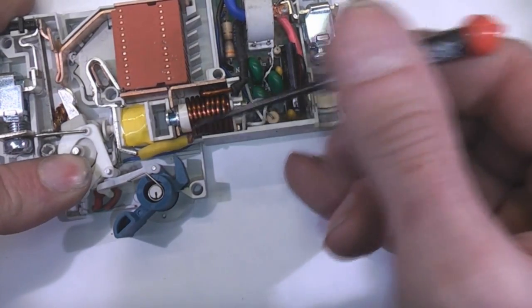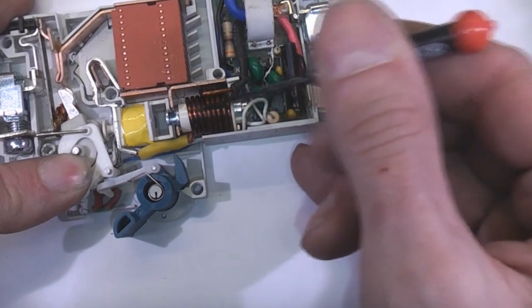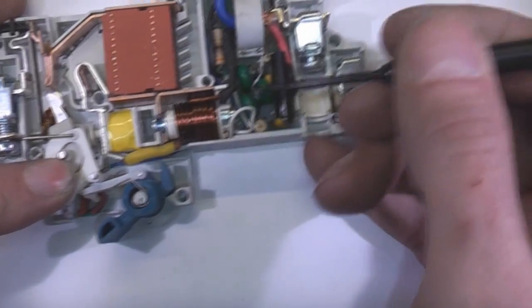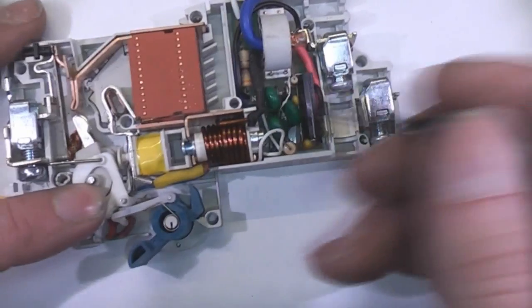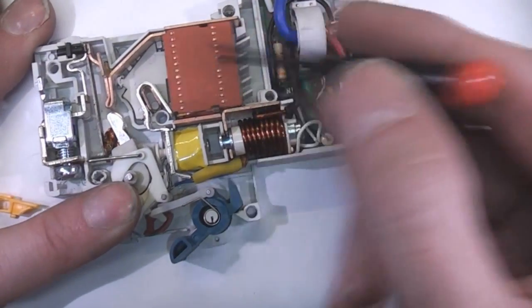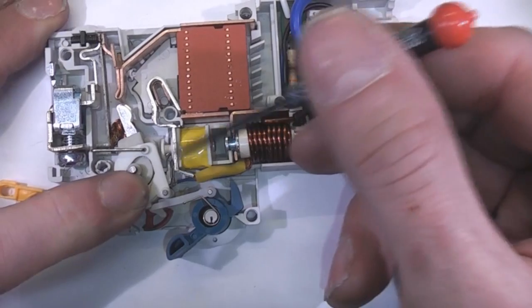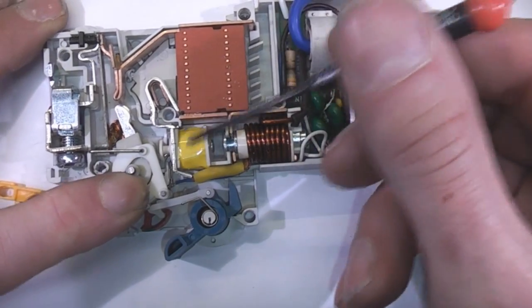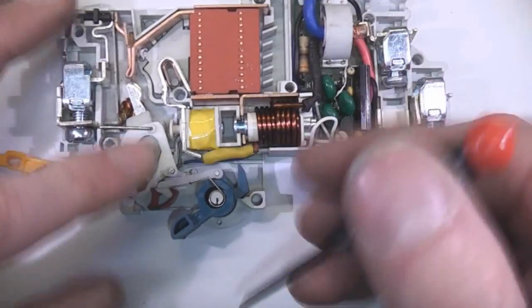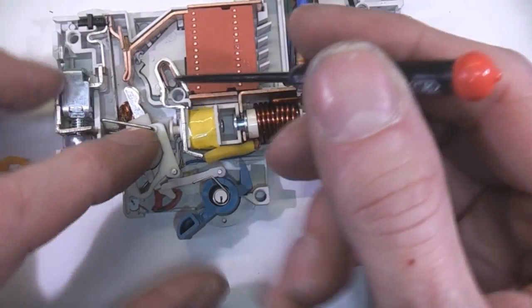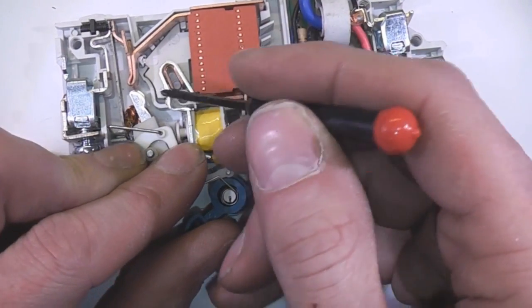And obviously on a higher current breaker, this would be a much thicker cable, fewer turns of a thicker wire, and that's what then goes out. Now this is the interesting stuff, because of course if you've got a high current circuit, when you turn it off, what happens, or what can happen, is you get an arc forming.